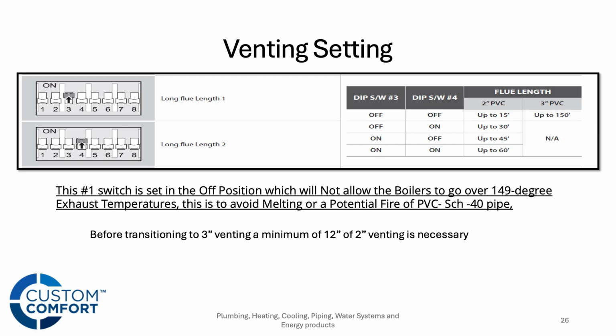If we need to go further than that, we're going to have to increase to 3-inch, where we can then go up to 150 feet. But in doing so, we've got to calculate the total equivalent vent length and then tell the boiler what that is. On 3-inch, not a lot of adjustment is needed, but on 2-inch venting is where we really have to make that calculation and then flip some dip switches based on how far we're venting. Up to 15 feet of total equivalent vent length, no adjustments are needed, but at 30, 45, and 60 feet, we're going to need to change some of those dip switches to tell the boiler what's going on there. A couple more things about the venting.